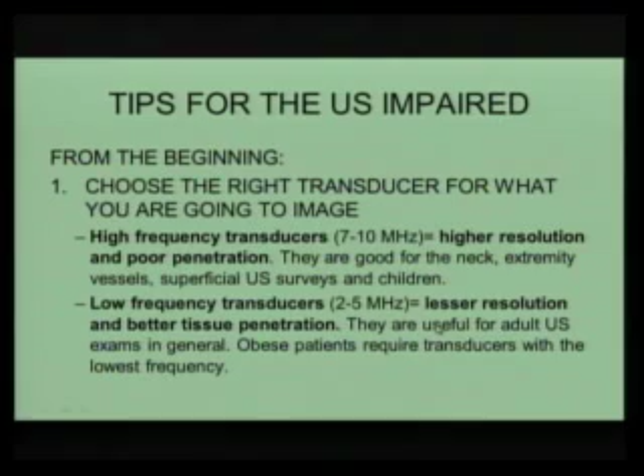Low frequency transducers, 2 to 5 megahertz: lesser resolution and better tissue penetration. They are useful for adults, ultrasound in general. Obese patients require transducers with the lowest frequency. And check on that. The other day we were doing an enormous man, and at the beginning we didn't see very well, and at the end we couldn't. But anyway, when you put on a 2.5 megahertz, for instance, you can see a little more. Which is the lowest megahertz that we have now? 2 to 5?